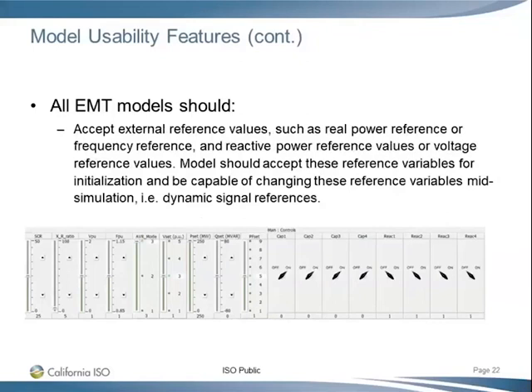And so this is talking about how all the external reference values should be adjustable, so we can easily change the voltage reference or frequency reference or the megawatt set point. So when we validate the model, we can run those tests to do a step change of the reference or set point. So we require you to include this feature. When you directly get a model from the manufacturer, those are probably not there. So that's why you have to add those to the manufacturer model.